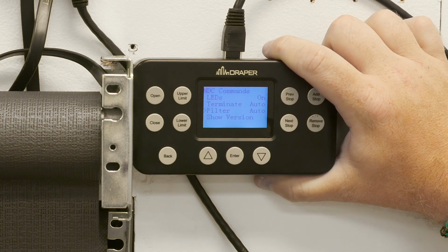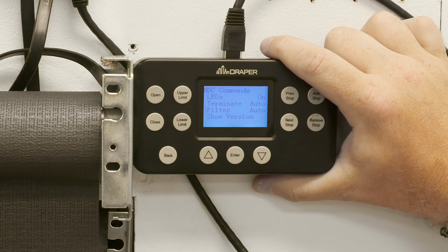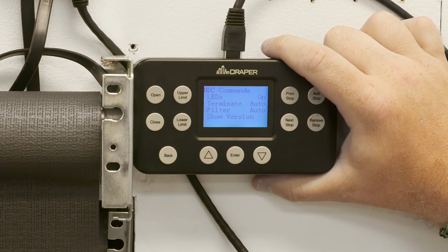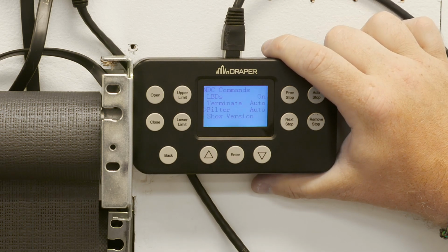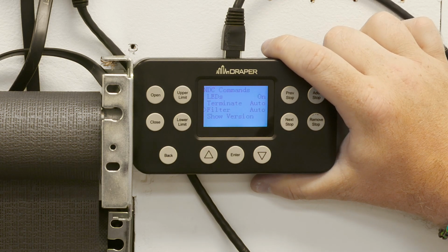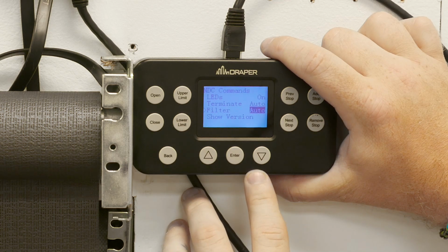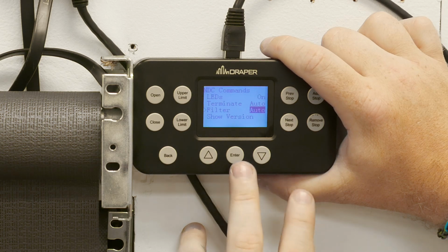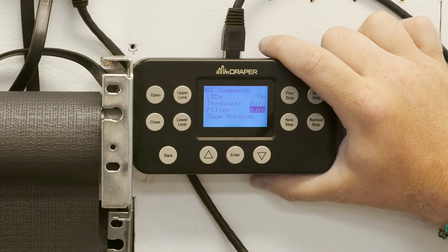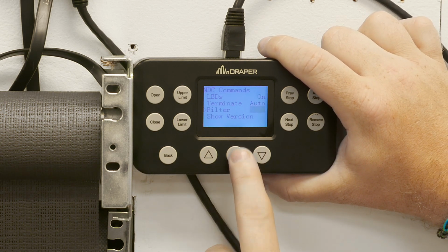Filter. As you can see on the NDC, we have 3 blue LEDs because each device port now has port isolation, meaning that they filter out any garbage that they may sense on the line due to faulty wiring, bad devices, something like that. Again, if you have an instance to where you need to turn the filter off for some reason, we have that built in. Again, by default, it's going to be set to auto filter. If you want to turn that off, you just simply highlight it, hit enter, select off, and hit enter again to save. Again, I prefer to have the filter on. It lets me know if I have issues on my network. So I'm going to go ahead and leave that to auto.